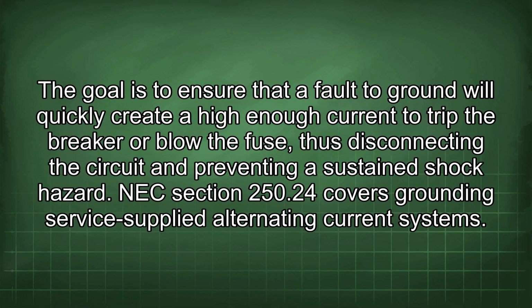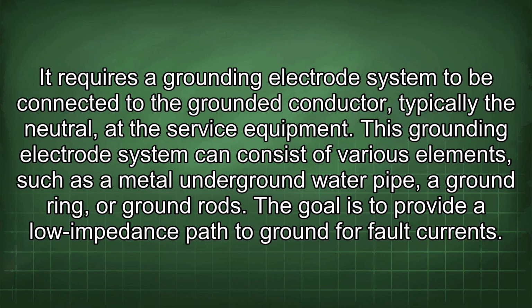The goal is to ensure that a fault to ground will quickly create a high enough current to trip the breaker or blow the fuse, thus disconnecting the circuit and preventing a sustained shock hazard. NEC Section 250.24 covers grounding of service-supplied alternating current systems. It requires a grounding electrode system to be connected to the grounded conductor, typically the neutral, at the service equipment. This grounding electrode system can consist of various elements, such as a metal underground water pipe, a ground ring, or ground rods. The goal is to provide a low impedance path to ground for fault currents.